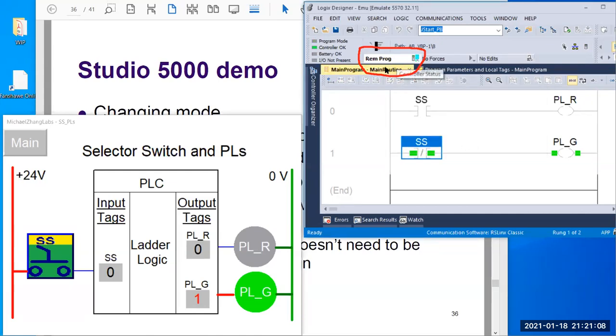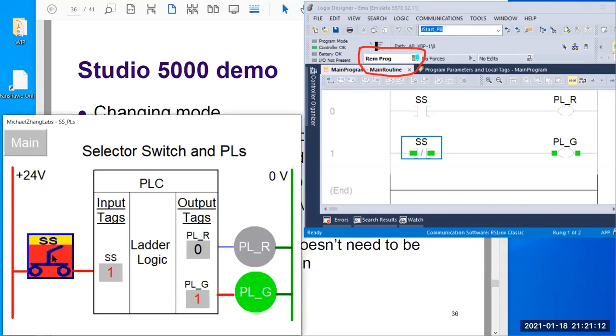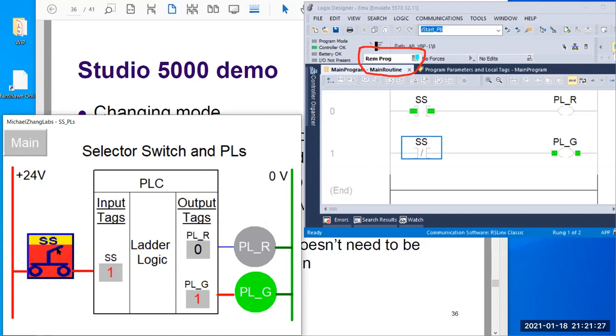Not only that — if you go into program mode, then let's switch on HMI — open close switch. This is what you may find puzzling. If you didn't pay attention, you can see this SS change. You may wonder: my SS is reflecting on the HMI, but why is the logic not running? My red light never turned on. Because your logic was never executed — even if this instruction is true, you don't have the power to turn on the output.